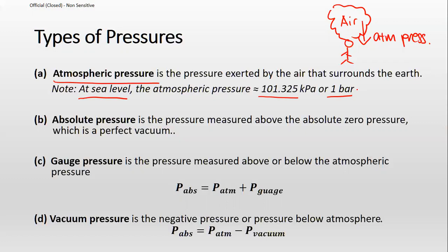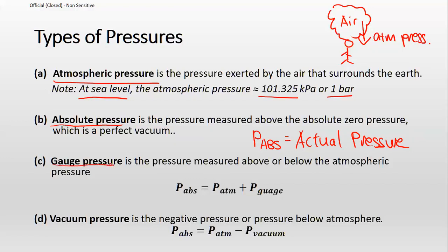Next, absolute pressure is defined as the pressure measured above the absolute zero pressure, which is a perfect vacuum. Essentially, P_abs is the actual pressure of your fluid or gas itself. Gauge pressure is the pressure measured by your instrument with respect to the atmospheric pressure. The formula is: P_absolute = P_atm + P_gauge. Typically, your instrument will measure the P_gauge, so if you want P_absolute, you add P_gauge plus P_atm.